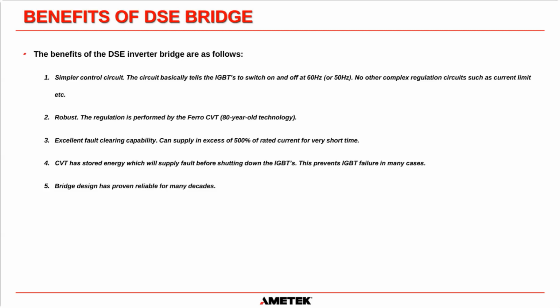They also have excellent fault clearing capabilities. The transformer can supply in excess of 500% of the rated current for a very short time. So let's say you have a 10 kVA UPS. That transformer will give you 50 kVA of energy to clear any short circuits if necessary. So they're very, very good at clearing faults on the load circuits if necessary.